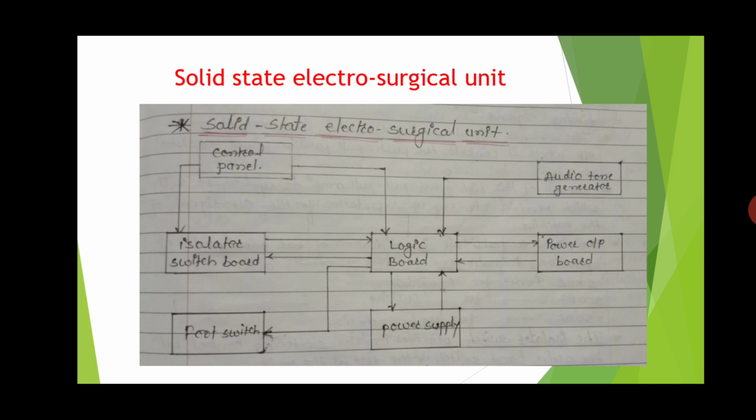The 250 kilohertz signal used for cutting is given to the power output, where it controls push-pull parallel power transistor output stages. The output of this high power push-pull amplifier is applied to a transformer which provides a voltage step up and isolation for the output signal of the machine. In order to facilitate identification of each mode of operation, the audio tone is generated with a different frequency.